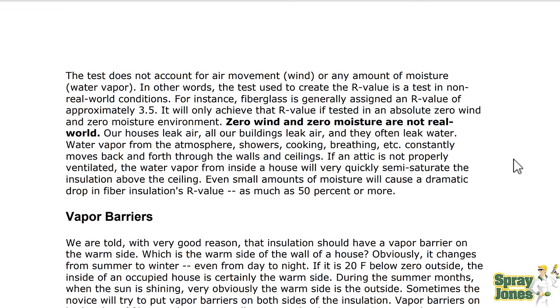The test does not account for air movement, wind, or the amount of moisture or vapor. In other words, the test used to create the R-value is a test of non-real-world conditions. For instance, fiberglass is generally assigned an R-value of approximately 3.5 per inch — it would only achieve that value if tested in absolute zero wind and zero moisture movement. Now, if you are doing an accurate, non-biased test for thermal conductivity, you do not want air movement because air movement would skew the results. You just want thermal conductivity — heat loss through conduction.